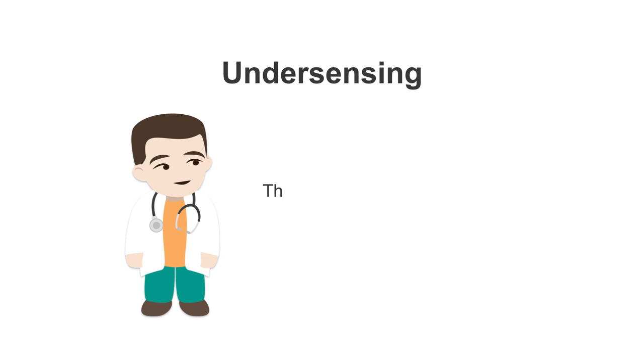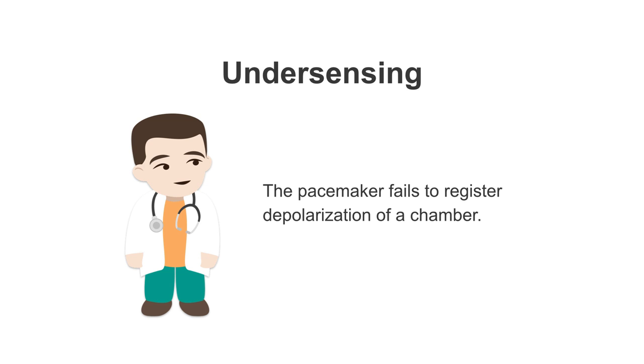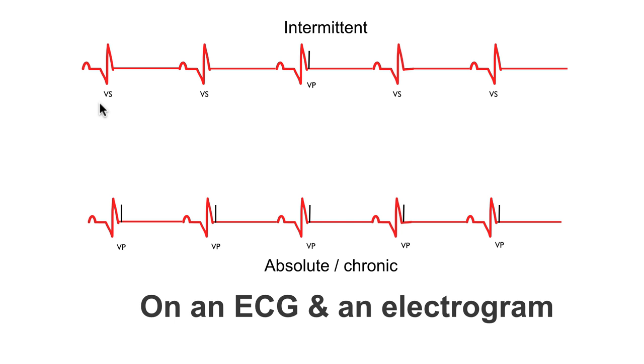Undersensing is where the pacemaker fails to register depolarization of a chamber. Let us have a look at how this may appear on an ECG.